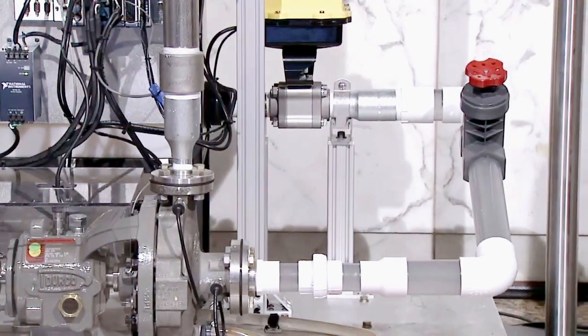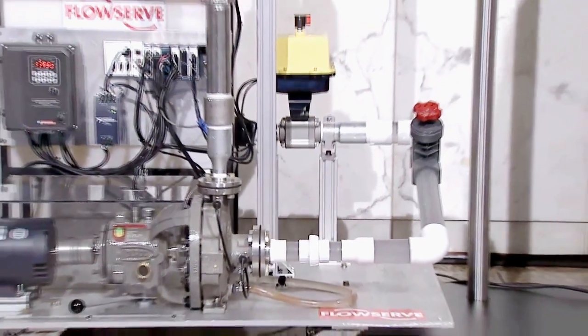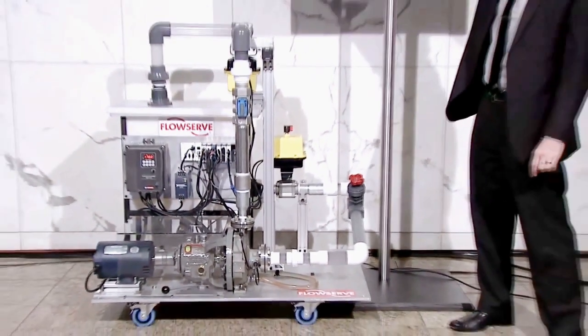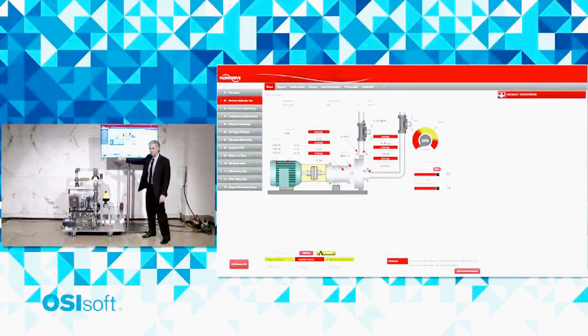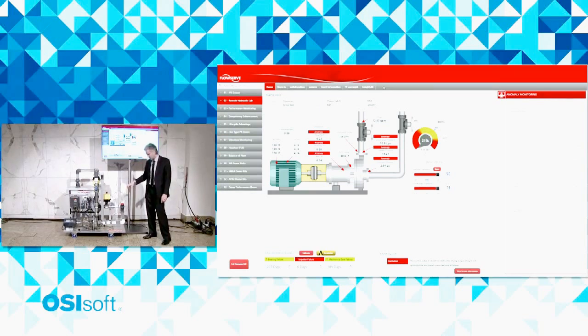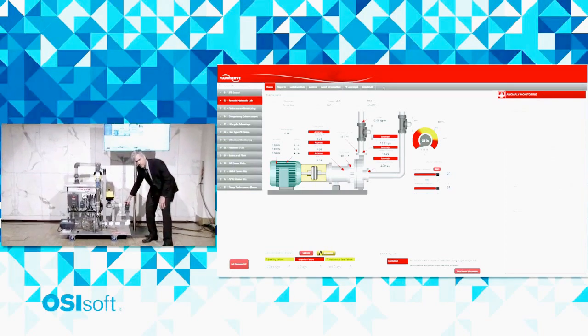And then in a moment here, what we'll see is that some of these indicators start to show red, which means it's detecting the failure, and it's predicting that in about 3 to 5 days, unless a technician addresses this issue somehow, we're going to have an impeller failure in this pump. And that'd be a big problem. But with this information, we can go out and make some changes, like, for example, remove the restriction from the line.